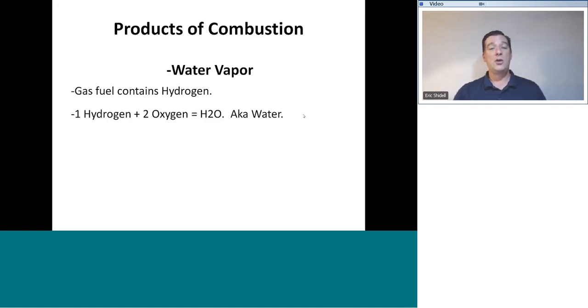This is why on a cold day in the winter, you see exhaust gas coming up out of the furnace flue. You can see it as a cloud because that water vapor hits that cold atmosphere outside, and, boom, turns into water droplets. It turns into a little cloud. In warmer weather, that doesn't happen because the water stays in vapor form when it hits the atmosphere. It doesn't cool down as much.